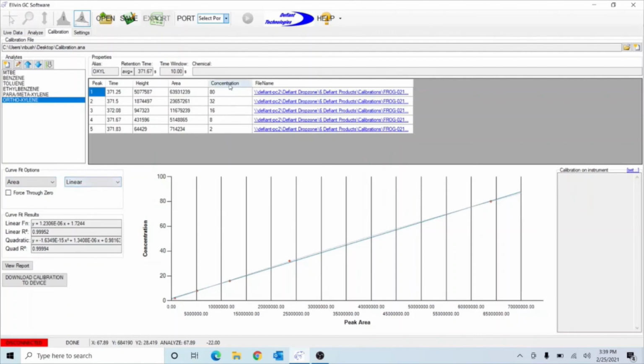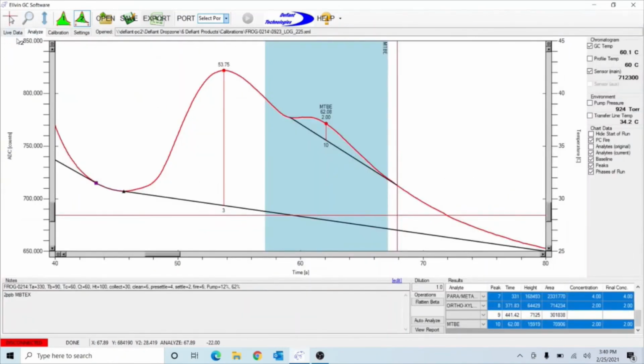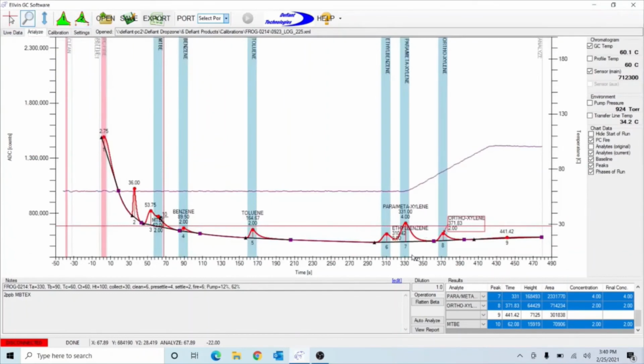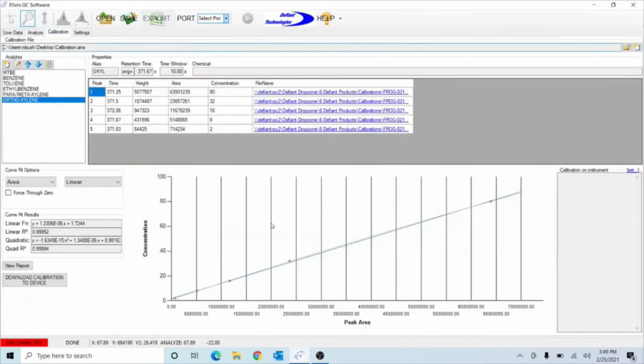You'll notice that all those 5 points we did make a graph over here. That's the line that we're talking about. This is how the software figures out what your concentration is. It looks at the reaction from the detector, at the reactivity of it. It looks at how big the peak area is, so it's going to measure the area underneath your curve. Then it's going to say if the area is this much, my concentration must be that much. That's why this is a critical first step.